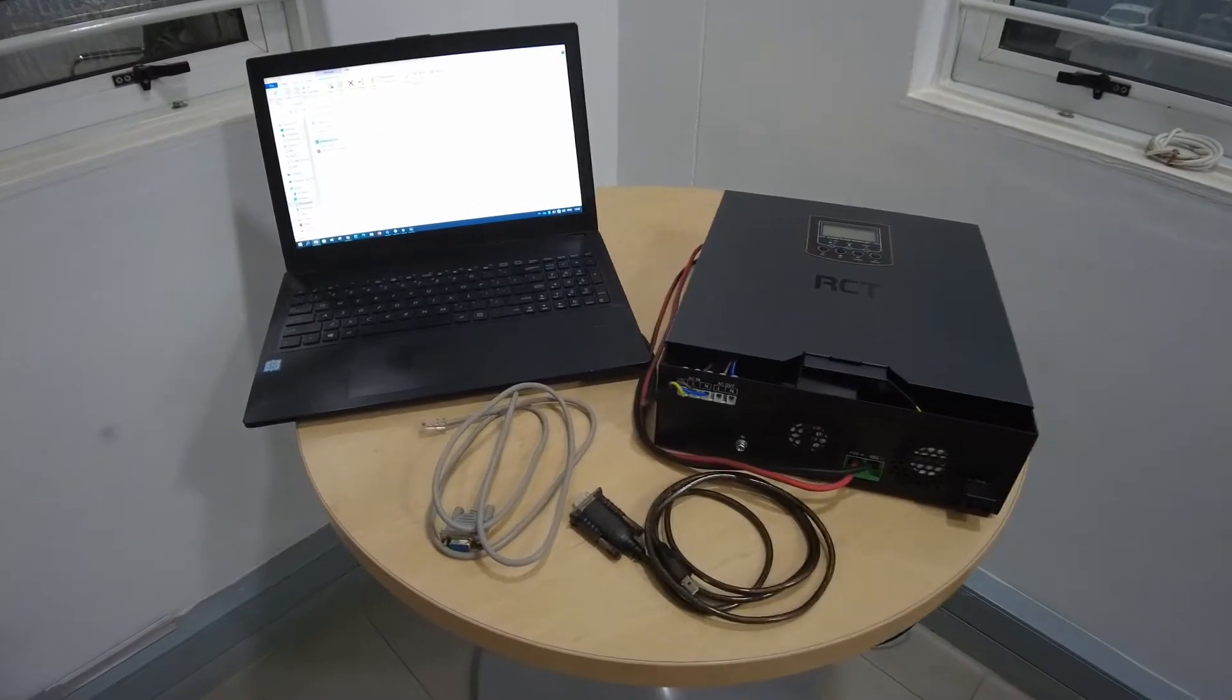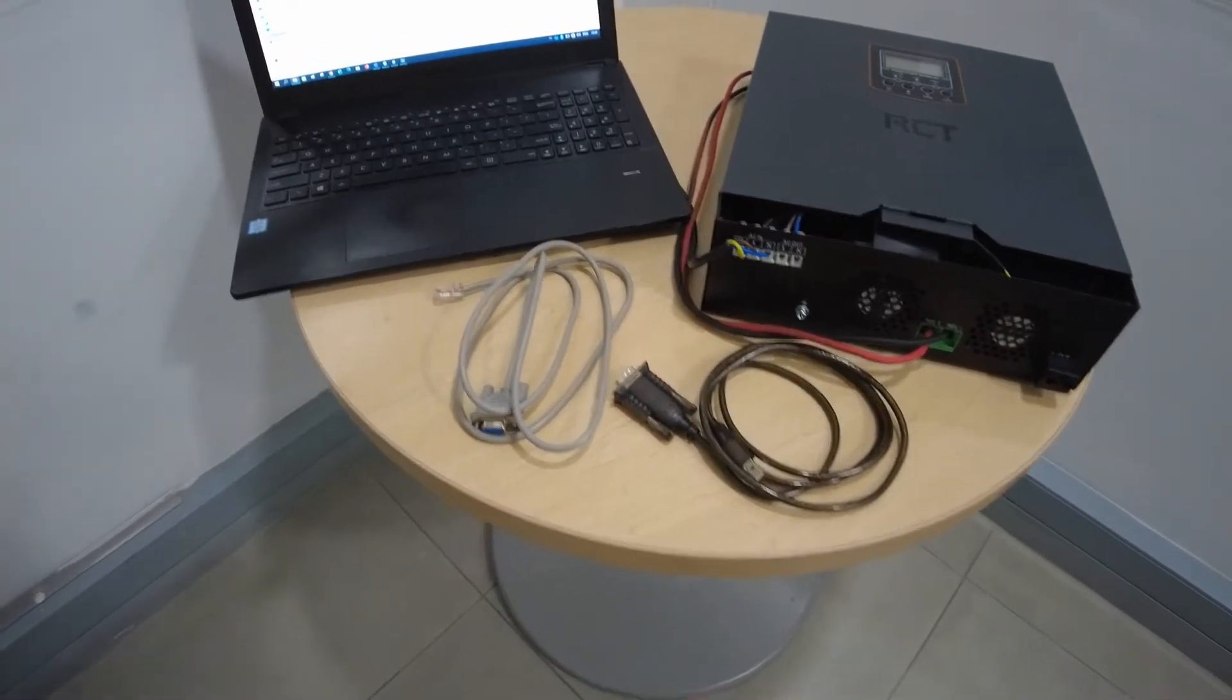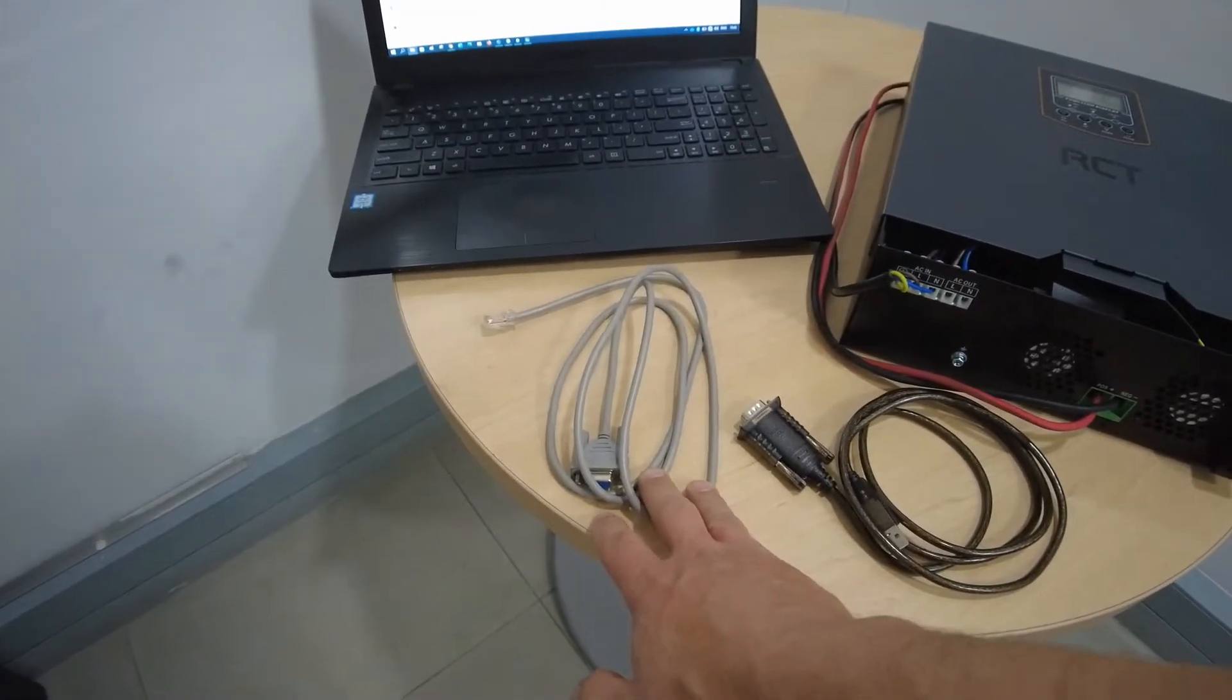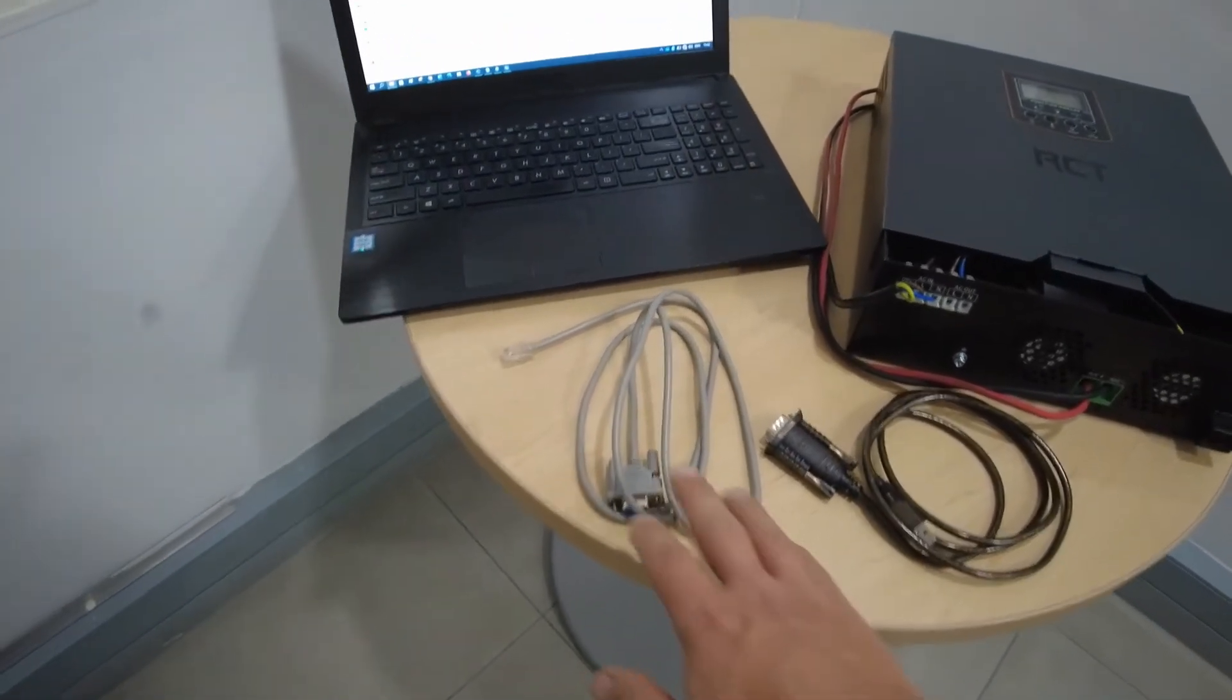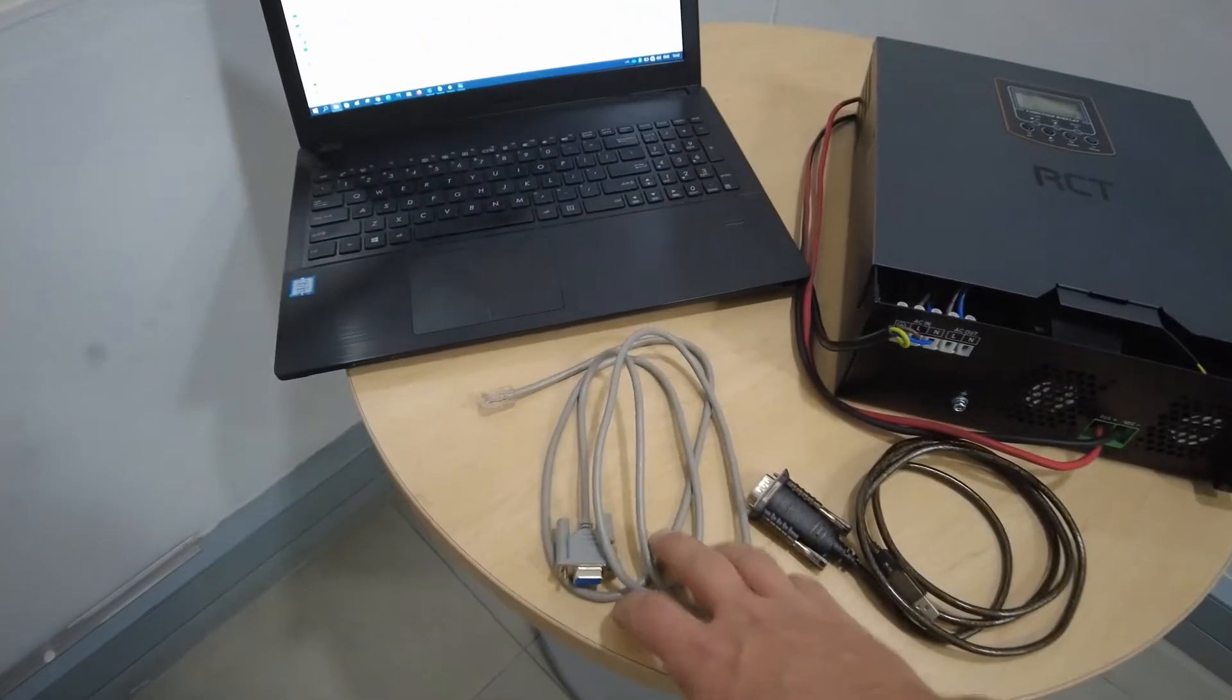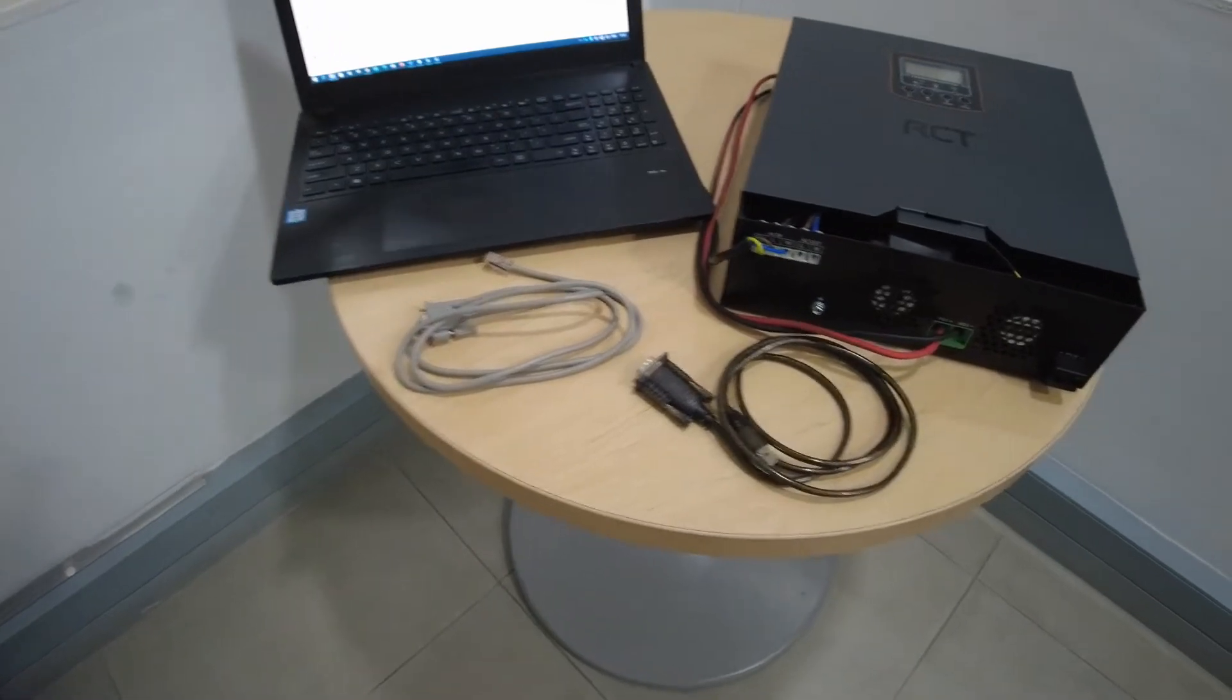As with previous firmware for other models, pay attention to the two cables you need. The gray cable comes standard with the inverter. Please find this cable and use it and do not find one online. If you lost the cable it will not work if you buy a cable online. The pin outs for this cable are different for RCT model inverters. So if you lost the cable you do need to find one specifically made for RCT inverters.